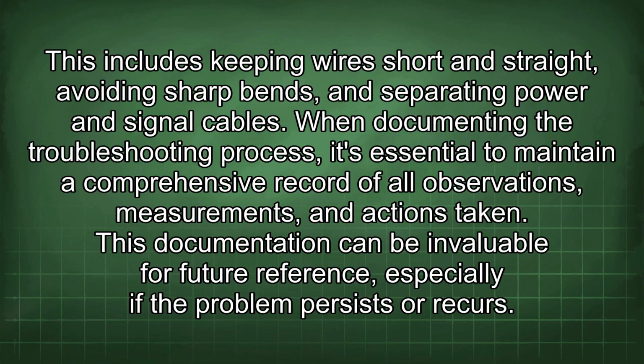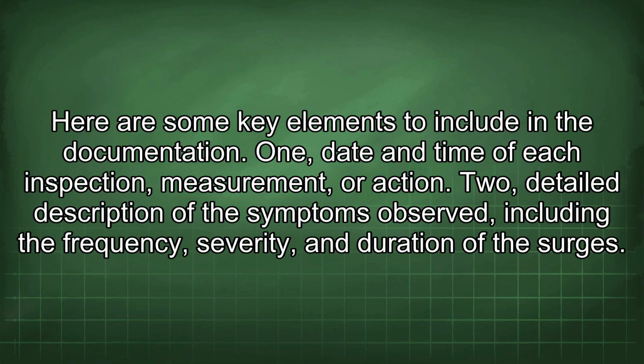When documenting the troubleshooting process, it's essential to maintain a comprehensive record of all observations, measurements, and actions taken. This documentation can be invaluable for future reference, especially if the problem persists or recurs. Here are some key elements to include in the documentation. 1. Date and time of each inspection, measurement, or action. 2. Detailed description of the symptoms observed, including the frequency, severity, and duration of the surges.